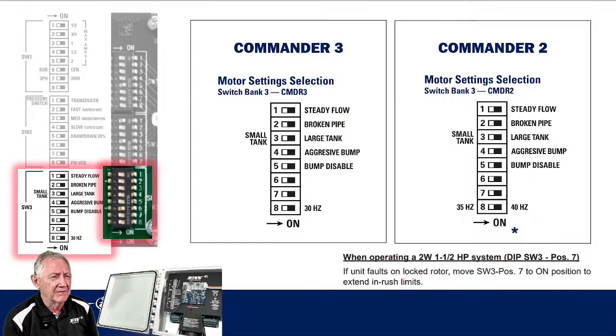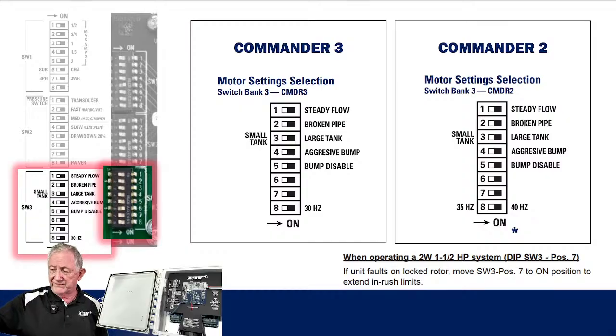And if they've got a conventional pressure tank in there and there's nothing wrong with it, leave it. There's no reason that it needs to come out. And there you can make that choice down there on position 3 to either go with the large tank or small tank. A lot of these are installed with tanks about the size of a basketball. They work just fine that way. All right, where are we at?